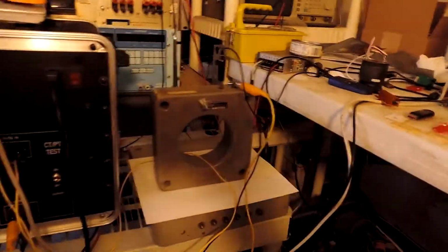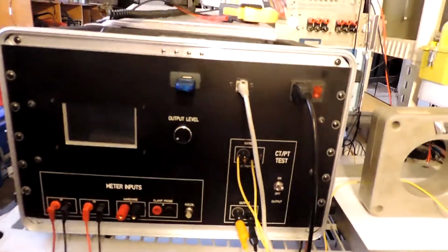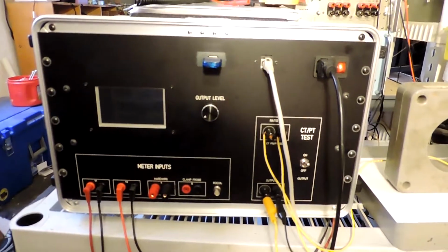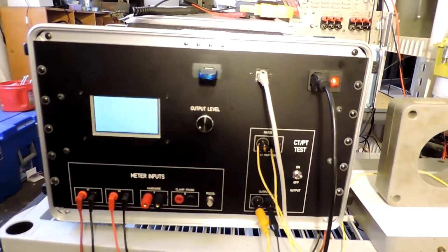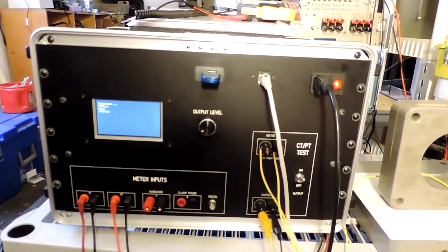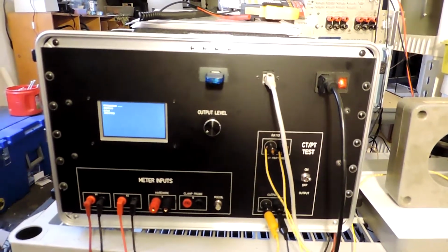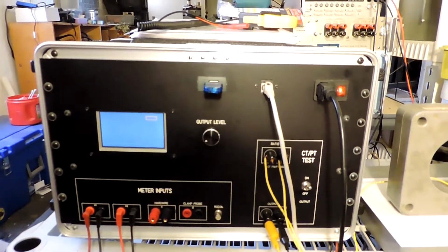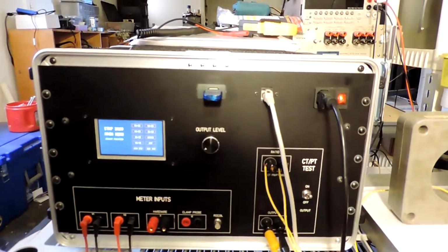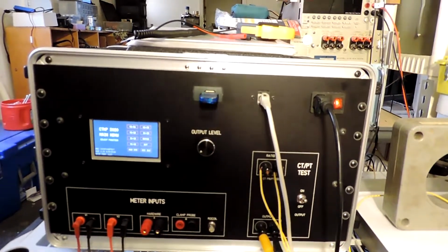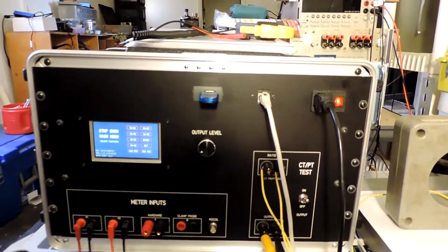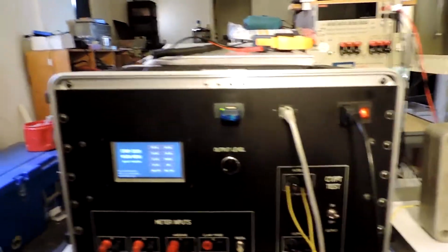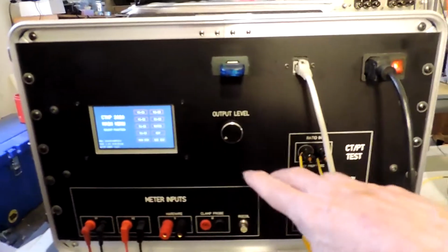What I'm going to do now is I have an 805 CT connected to the CTMP 2020. I'm going to turn the CTMP 2020 on. It has downloaded that heading data, the substation, the breaker number, and the job number, and has opened a file on the flash drive with that data, so that as I test the CT, the data will be appended under that heading, so you'll know which CT that data belongs to.